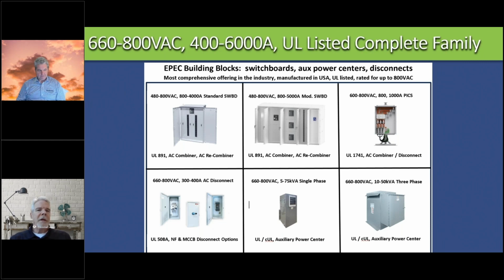So we really, again, want to build emphasis and educate on what's available for 800 volt, or 660, 690 to 800 volt. We actually have a product family, and I just wanted to go through this quickly because I think it's important to know that products are available out there. So the top left is our standard switchboard, like you just saw.